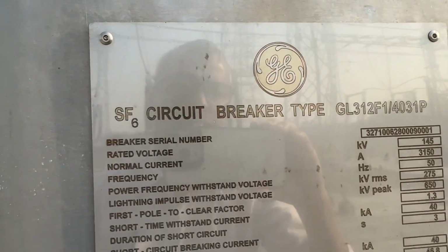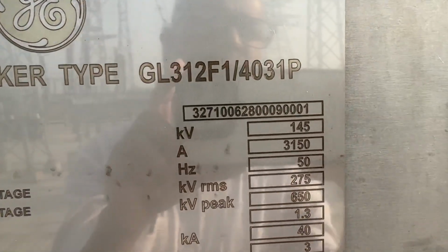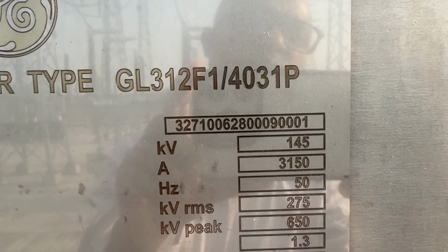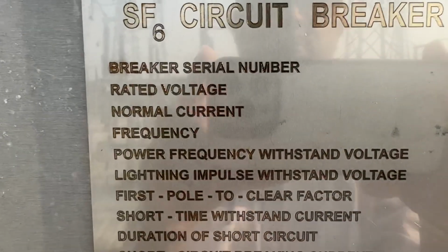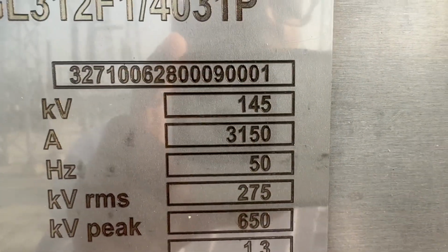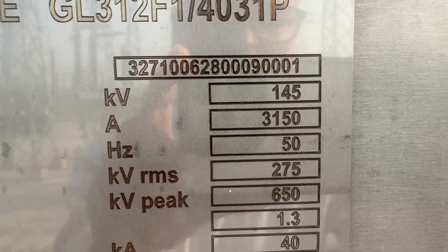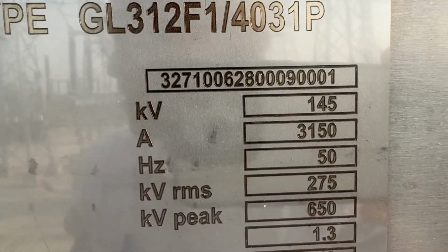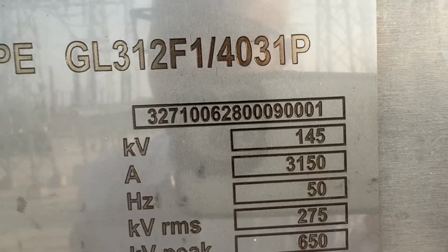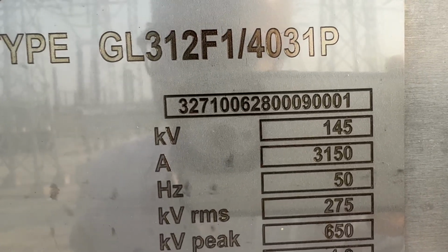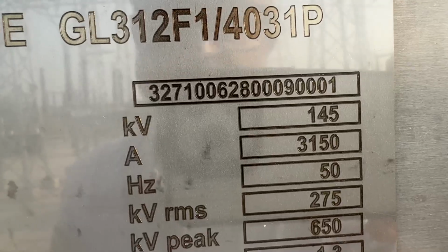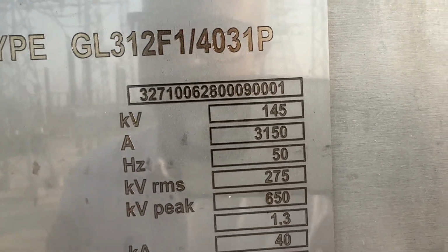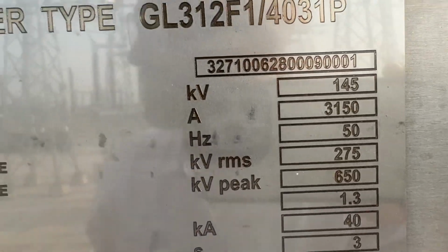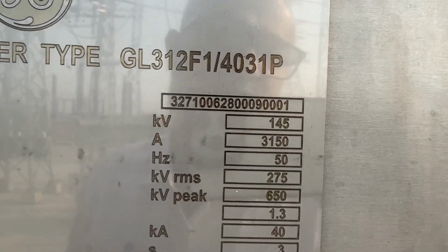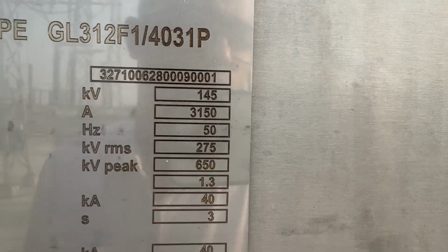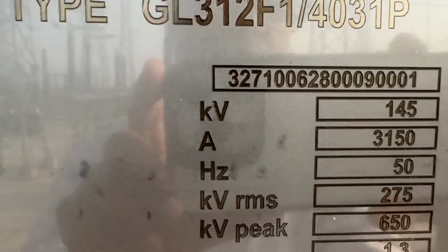There is a rating plate: SF6 circuit breaker, type GL312F1/4031P. Okay. Rated voltage, nominal current. Rated voltage is 145 kV. It is mentioned here that all 132 kV systems are rated to a maximum of 145 kV. It is applicable for the circuit breaker, current transformer, every piece of equipment on the 132 kV side. And for a 230 kV system, the maximum rating is 245 kV.